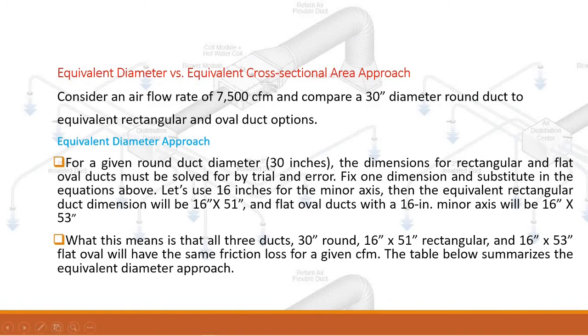Equivalent diameter versus equivalent cross-sectional area approach. Consider an airflow rate of 7500 CFM and compare a 30-inch diameter round duct to equivalent rectangular and oval duct options. For a given round duct diameter of 30 inches, dimensions for rectangular and flat oval ducts must be solved by trial and error. Fixing the minor axis at 16 inches, the equivalent rectangular duct dimension will be 16x51 and the flat oval duct with a 16-inch minor axis will be 16x53. This means all three ducts — 30-inch round, 16x51 rectangular, and 16x53 flat oval — will have the same friction loss for a given CFM.